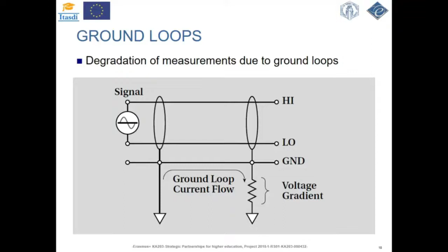Ground loops can occur in any type of measurement system, but they are most problematic for analog measurements. For ground referenced measurements, a ground loop results in currents which flow through the cable shields. On the other hand, in the case of differential measurements, the ground loop voltage can contribute to the common mode voltage. As a result, we can have measurements which are degraded by noise or suffer from a reduced signal input range.